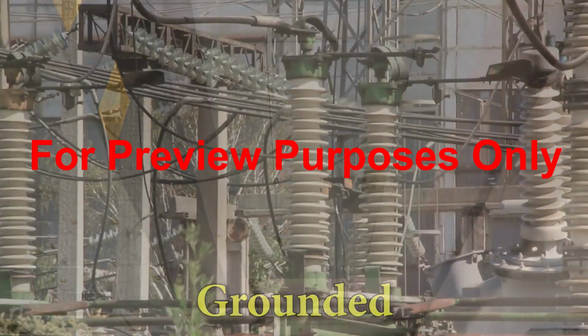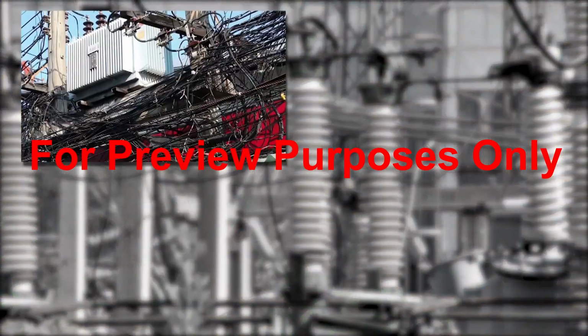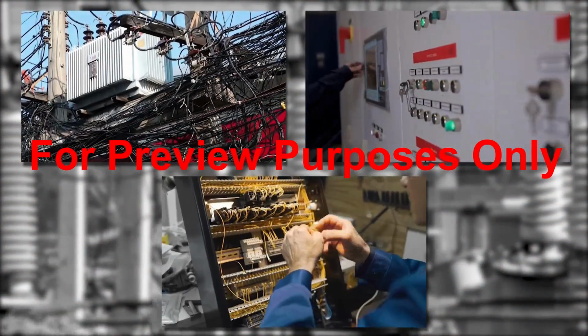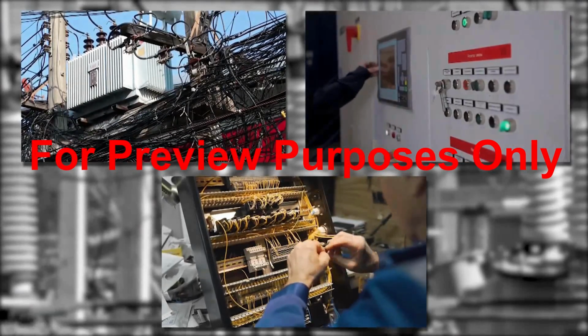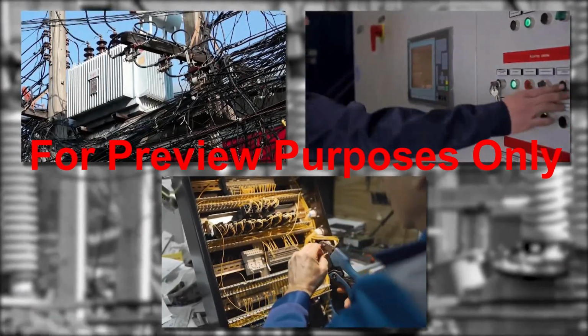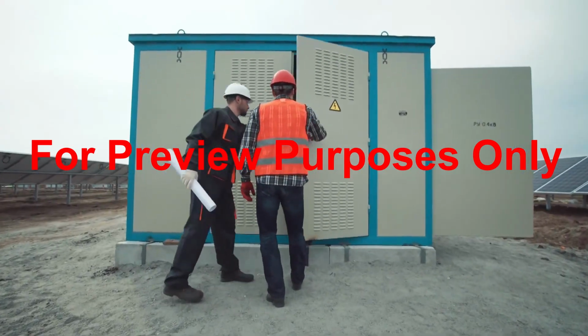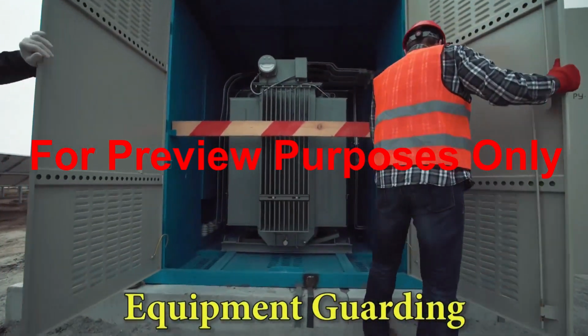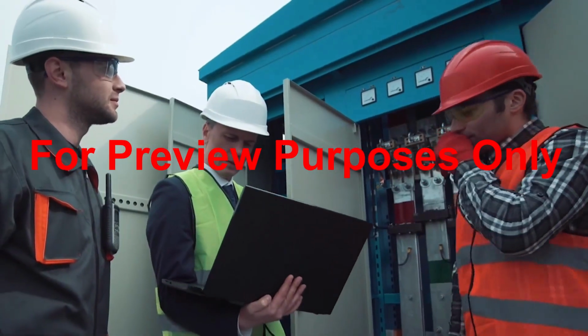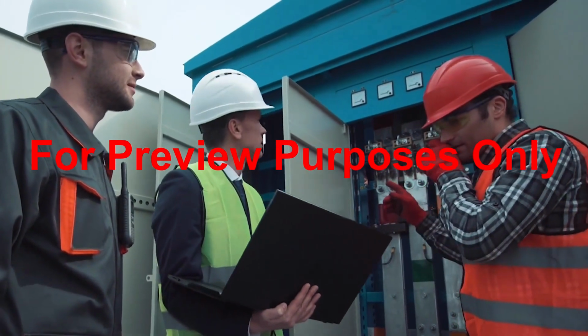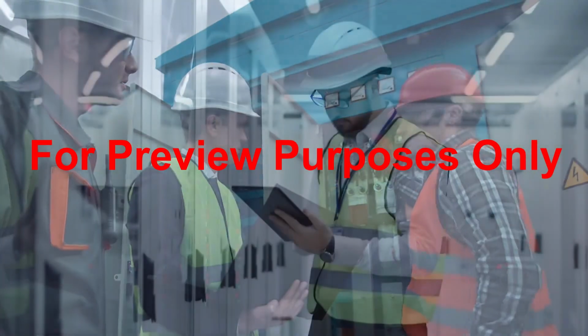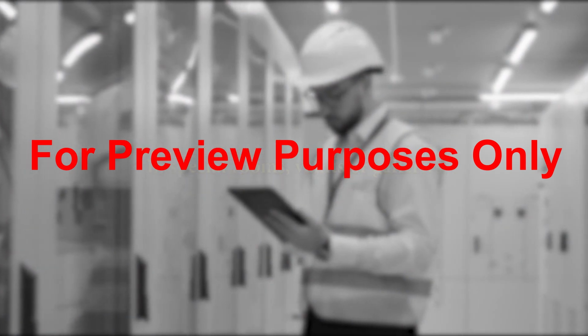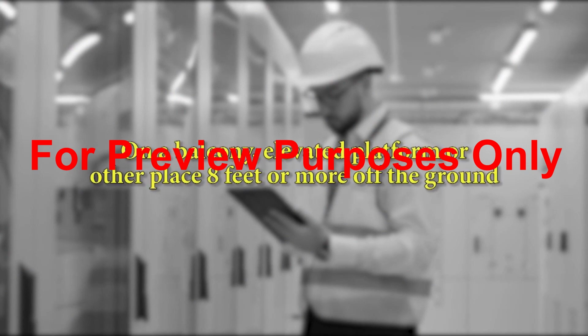A cover or faceplate should be installed, and if the parts are made of metal, they should be grounded as well. High-voltage electrical equipment such as transformers, switchgear, and distribution boxes can create serious electrocution hazards, especially for workers who are not familiar with how they work. So equipment rated at 50 volts or higher is kept separate or guarded on a job site. This allows access to be limited to those who are qualified and authorized to work with the equipment safely. Equipment can be guarded by locating it inside an enclosure or behind permanent screens, in special rooms, vaults, or galleries, or on a balcony, elevated platform, or other place that is 8 feet or more above the ground.